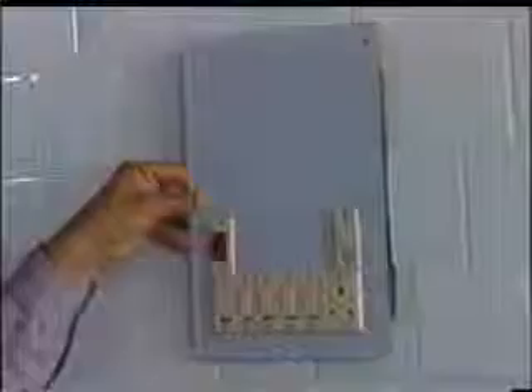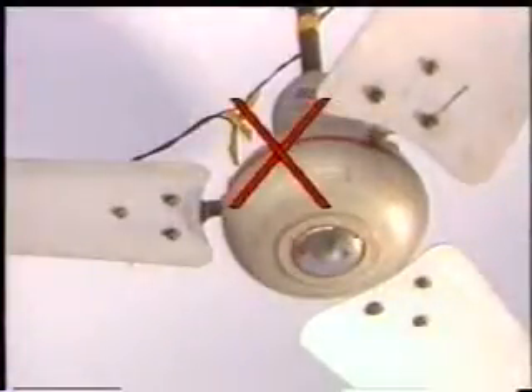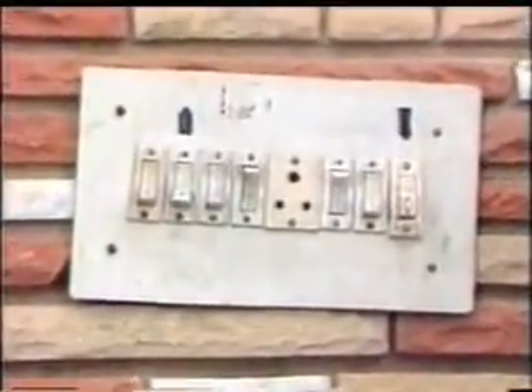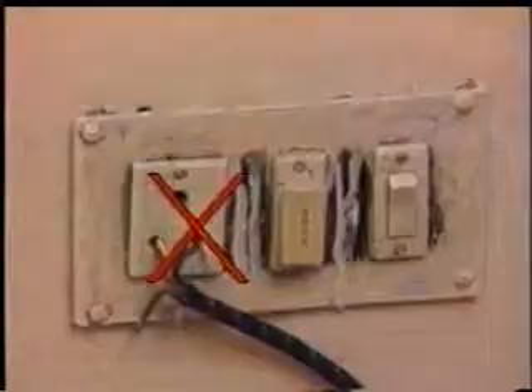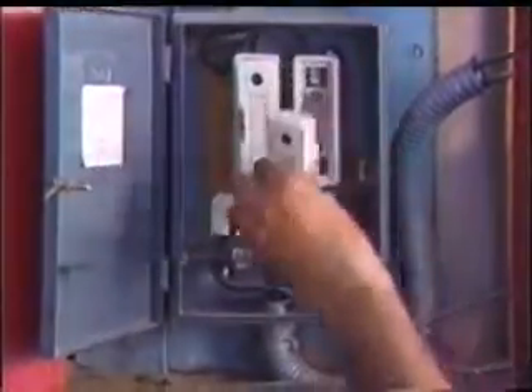Here are certain additional guidelines for carrying out proper wiring. Length of PVC cables should not fall short. Maintain proper geometry. Avoid too many extensions of circuits. Provide switches at convenient height. Use proper plug top for safety reasons. Do not replace fuse grip with cable. Use proper fuse.